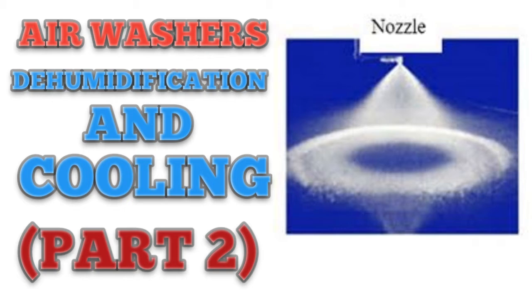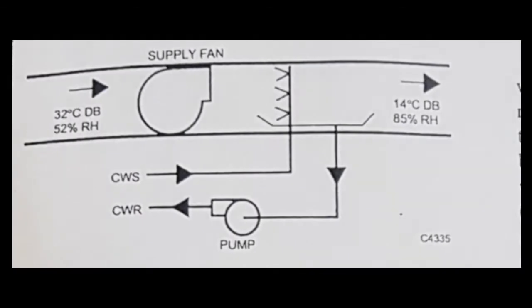This figure illustrates an air washer system used for cooling and dehumidification. The chiller maintains the washer water to be sprayed at a constant 10 degrees centigrade. This allows the chill water from the washer to condense water vapor from the warmer entering air as it falls into the pan.